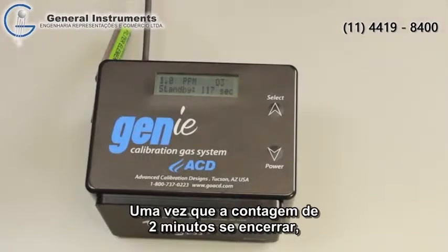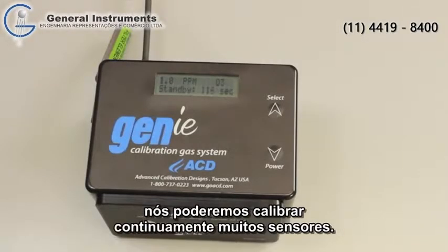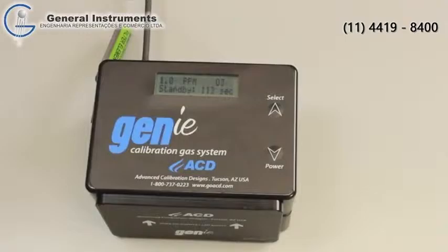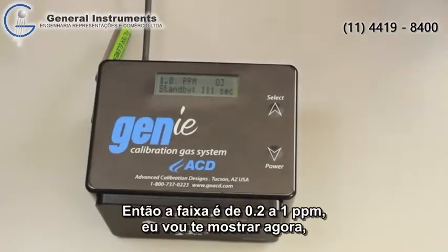Once the 2 minutes is counted down, we can continuously calibrate until we get tired of calibrating. We can do tons and tons of sensors with this. So the range is from 0.2 to 1 part per million.